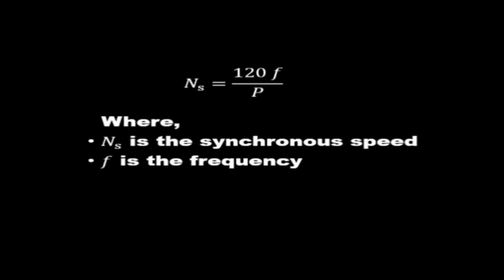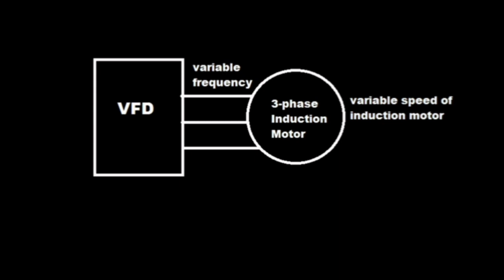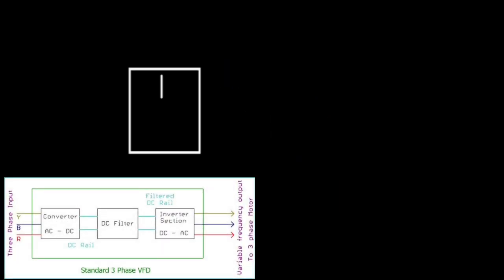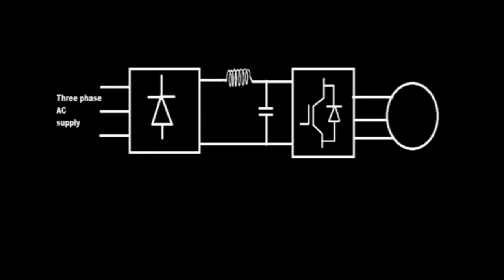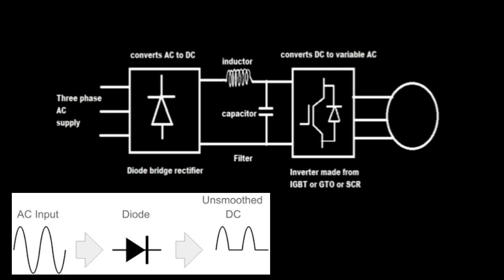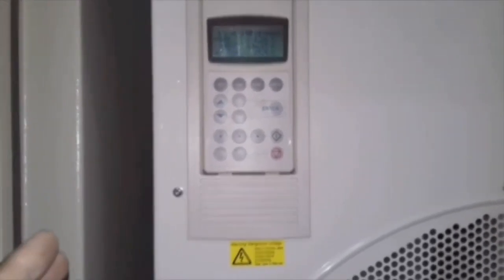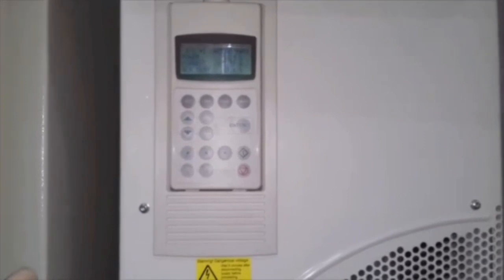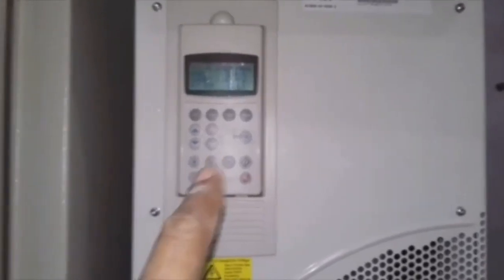When we apply a three-phase supply to the converting circuit, it converts into DC — but not pure DC; it is a pulsating DC. In the converting section, diodes are commonly used to convert AC into DC. The three-phase supply lines R, Y, B are connected to the converting section, and it converts them into DC.